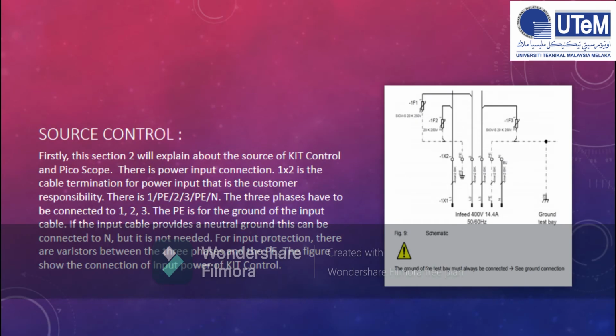Okay. For section 2, we explain the source of Kit Control and PicoScope. There is the power input connection. 1X2 is the cable termination for power input, which is the customer's responsibility. There is terminal 1, terminal 2, terminal 3, terminal PE and terminal N. The three phases have to be connected to 1, 2, 3. The PE is for the ground of the input cable. If the input cable provides a neutral ground, this can be connected to neutral, but it is not needed. For input protection, there are varistors between the three phases and the PE. The figure shows the connection of input power of Kit Control.